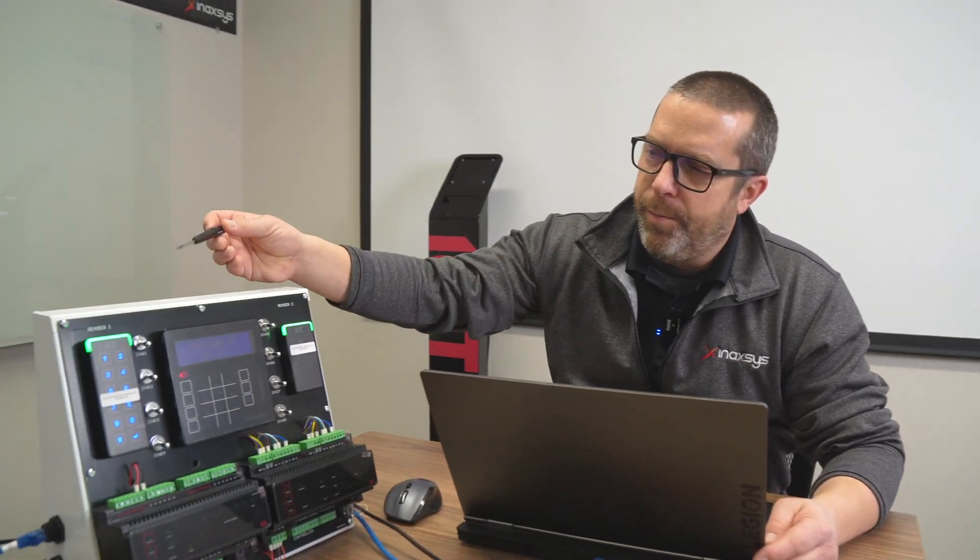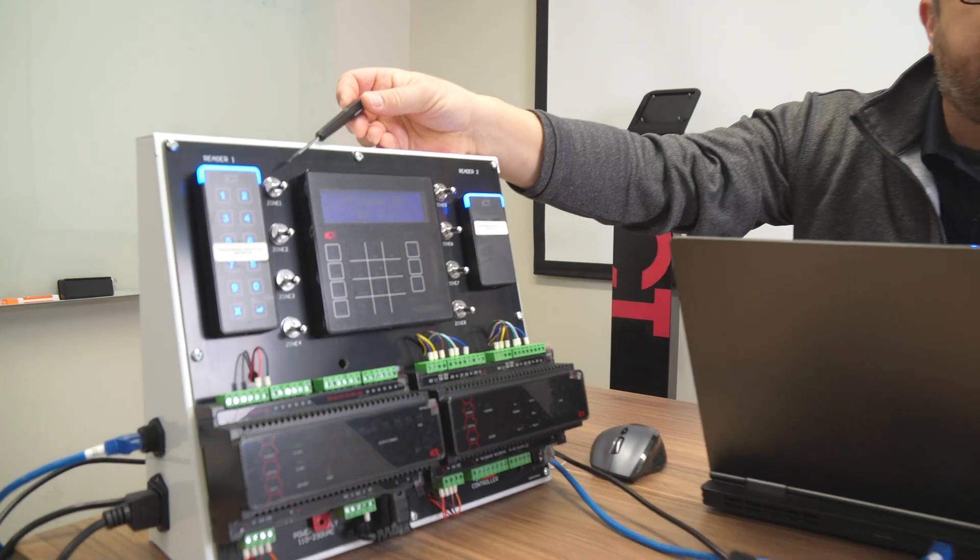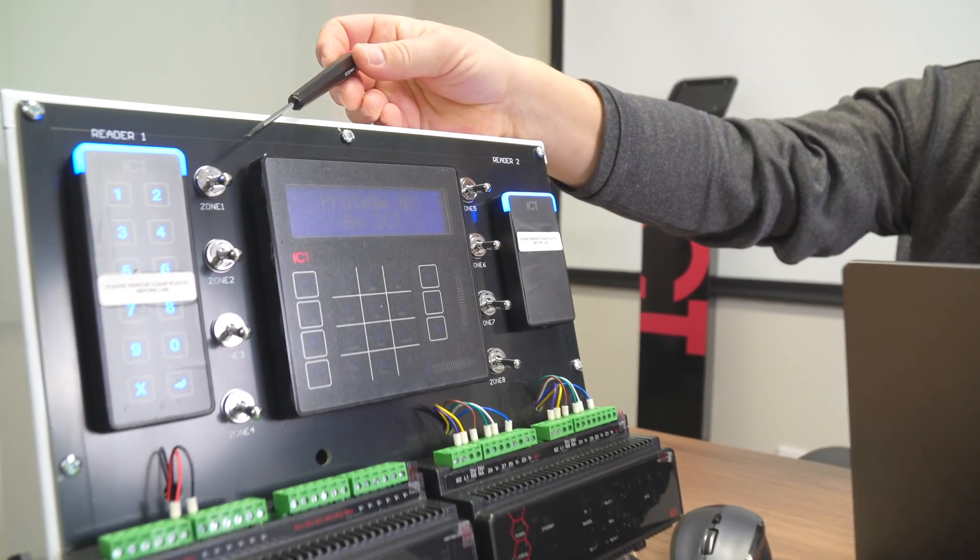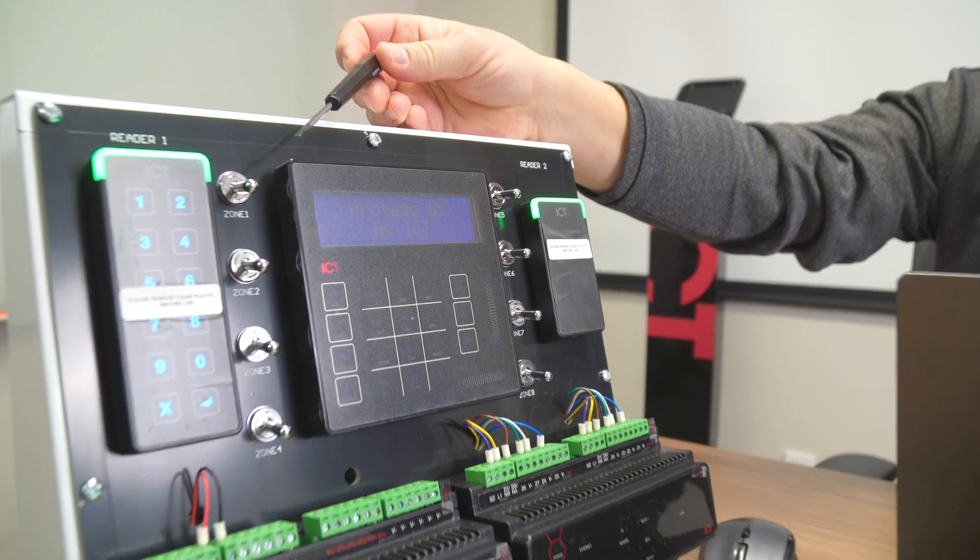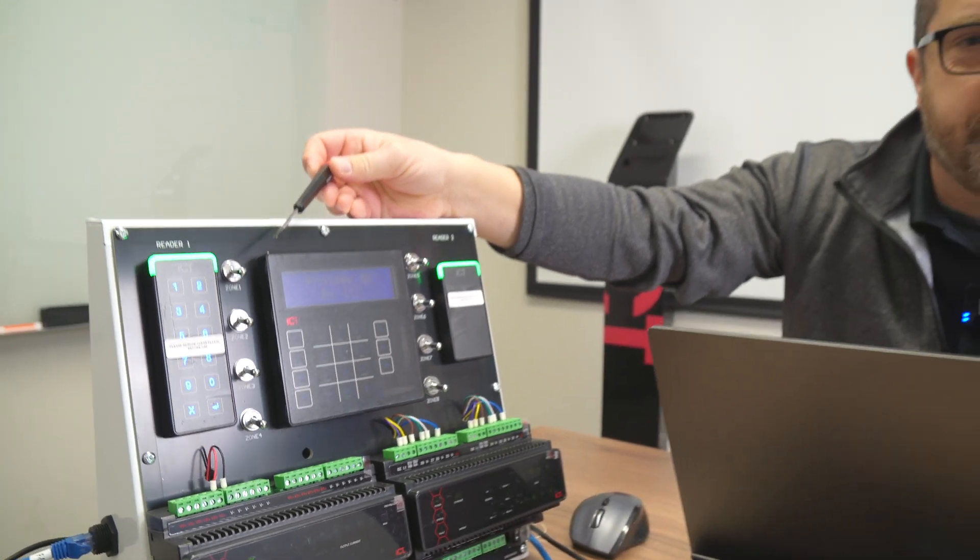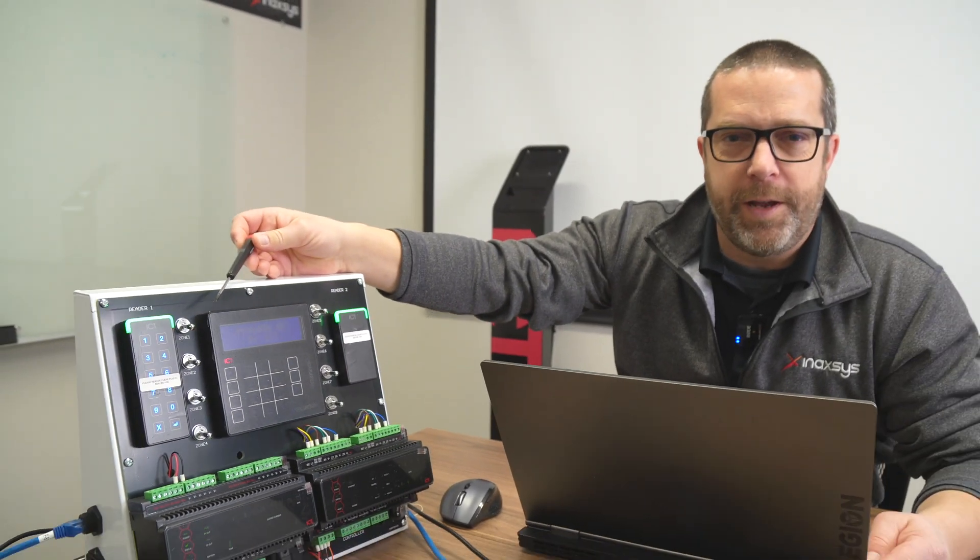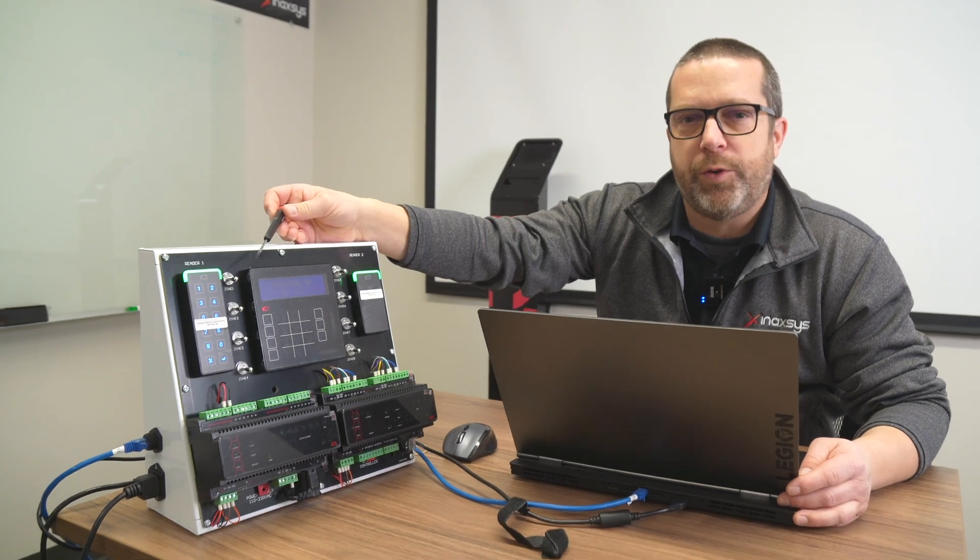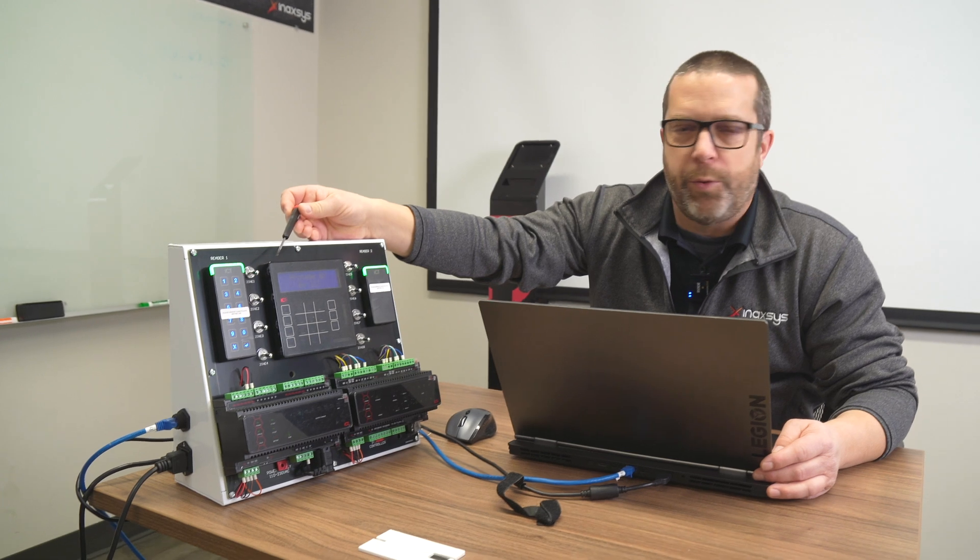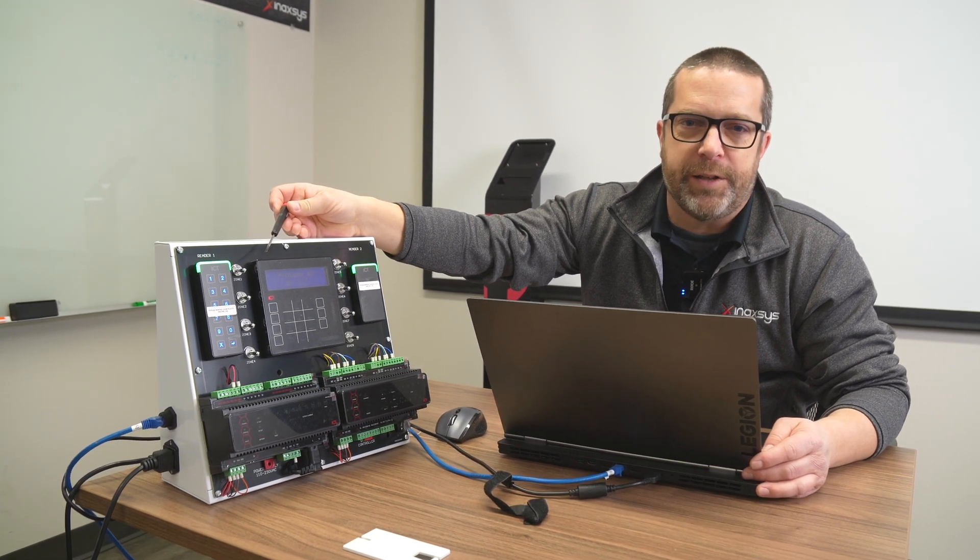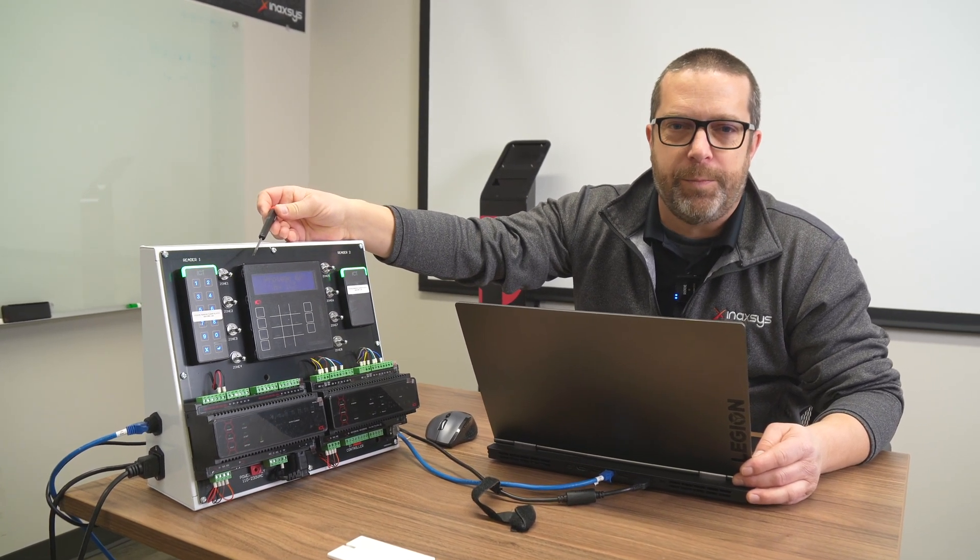In today's video, I will show you how to enable the Prodigy GX Denable Controller onboard reader ports. As you can see on this demo kit, my readers are flashing blue and green. This means that the readers are programmed for RS-485 communication, but the controller is not ready or not programmed for RS-485, which is the default. I will show you how to enable the onboard reader ports for RS-485 communication so that the readers communicate properly and then we can start using them for access control.